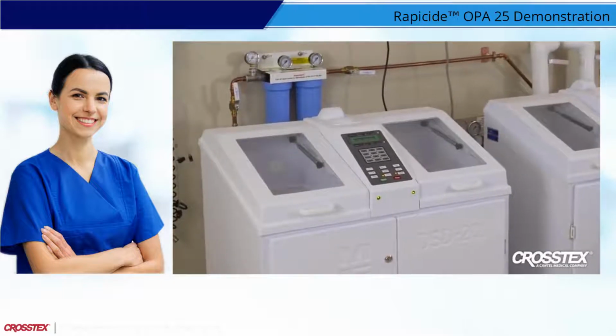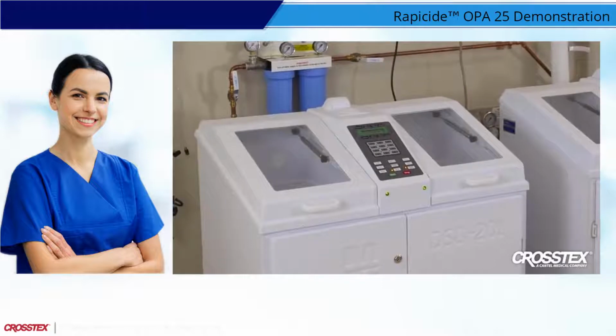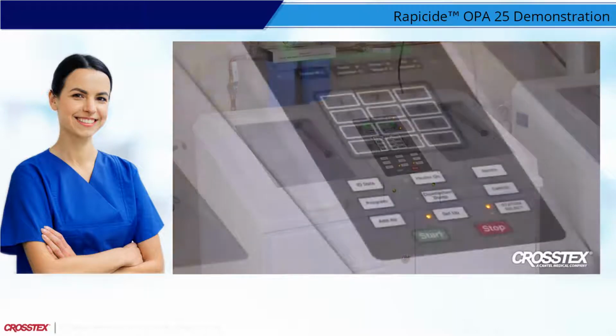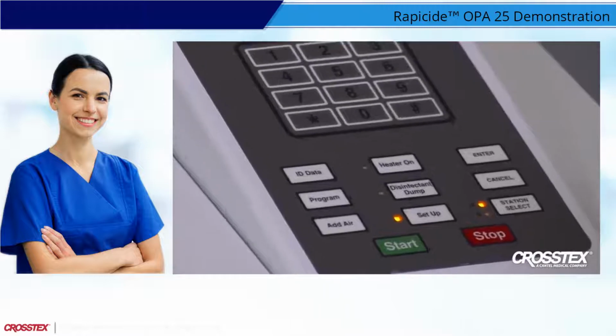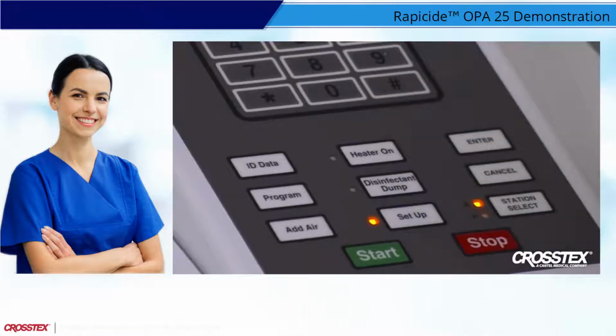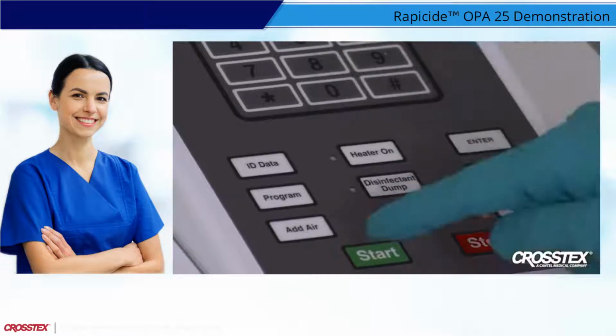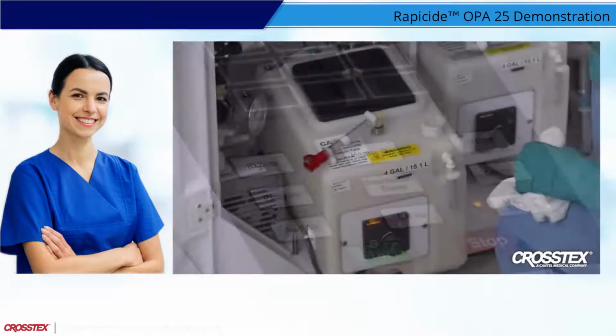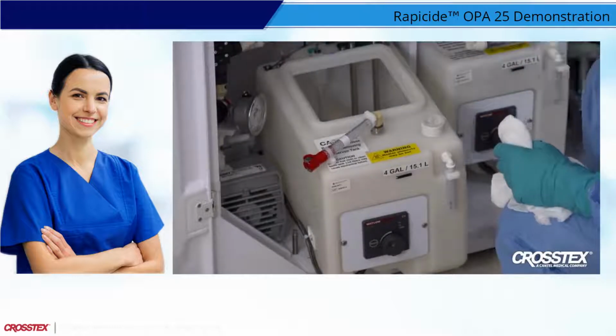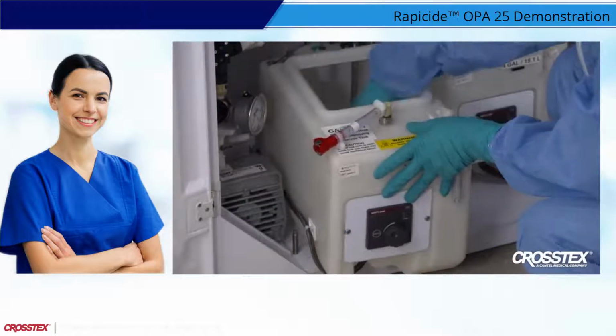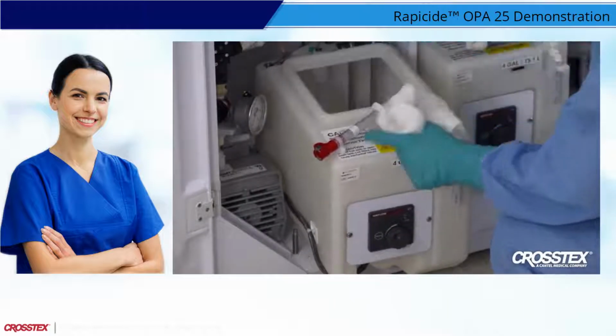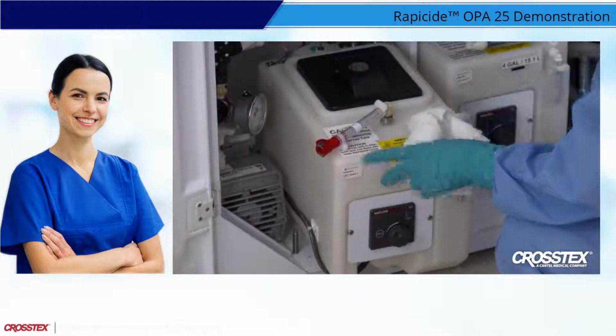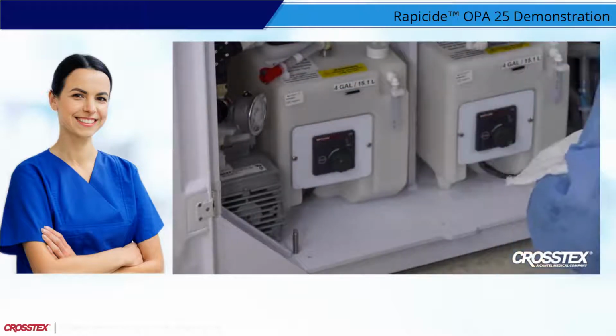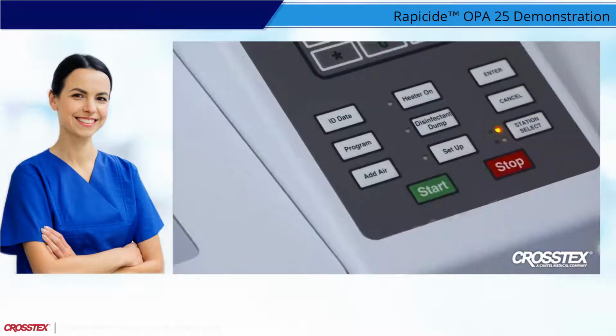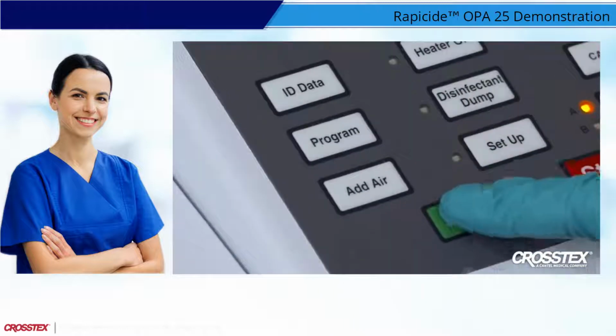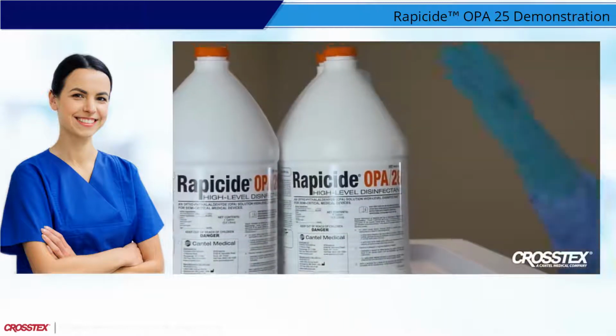To clean out when switching from one type of disinfectant to another in the Medivators DSD reprocessor, follow these steps. Remove the existing disinfectant by evacuating it from the reservoir tank. This can be done by pressing the disinfectant dump and start keys on the AER control panel. Visually ensure that the reservoir tank is empty. Remove the tank and wipe it clean with a damp, lint-free cloth. Refit the tank in the machine. Fill the reservoir tank with fresh water. Run 2 standard cycles with the fresh water and dump again, using the same control panel process as before. The Rapicide HLD solution is now ready to be added.